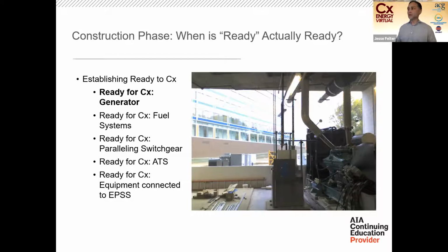In this particular case, the engine on that generator was ready to load bank. But what the installer wasn't aware of was an NFPA 110 requirement - not Jesse's, not Mark's requirement, an industry standard - that the enclosure of the generator is part of the gen set.